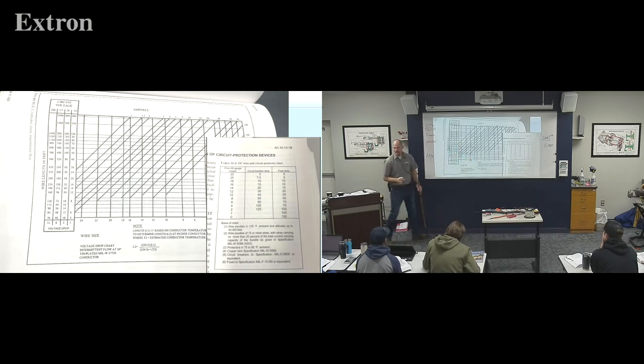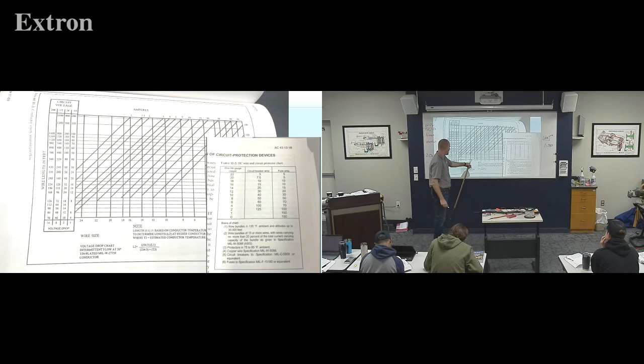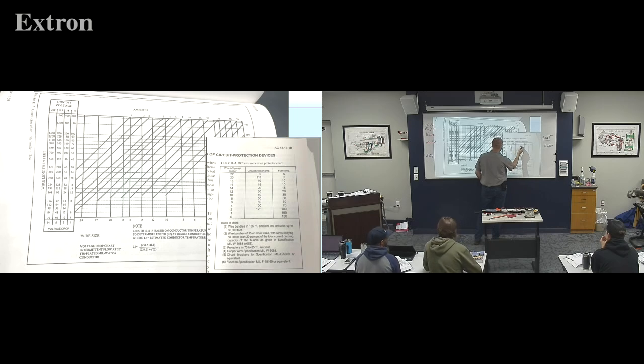Wow, he's good. 20 gauge, did you do the next step though? Oh no, all right, let's go back to the next step. We know we have to run at least 10 amps through it. If we run a 20 gauge wire, what circuit breaker will work for my 20 gauge wire? Oh, snap. I can only run 7.5 amps through my 20 gauge wire.